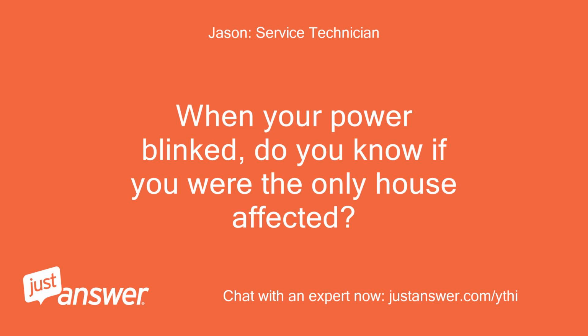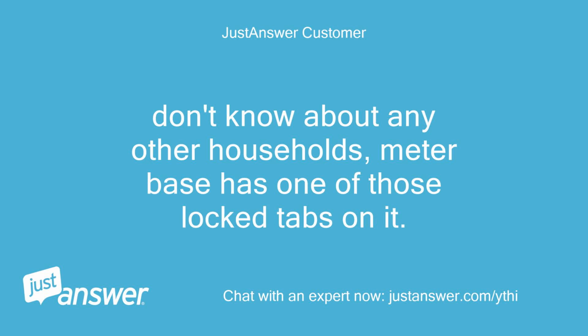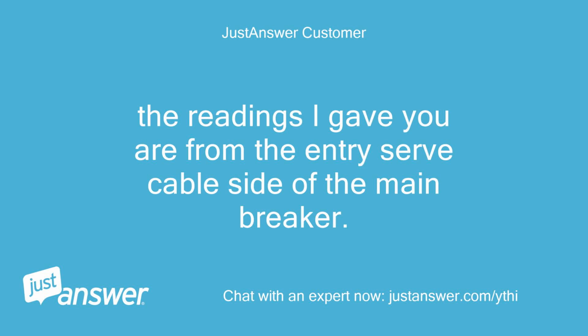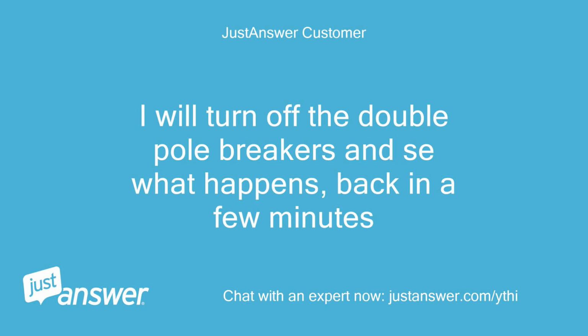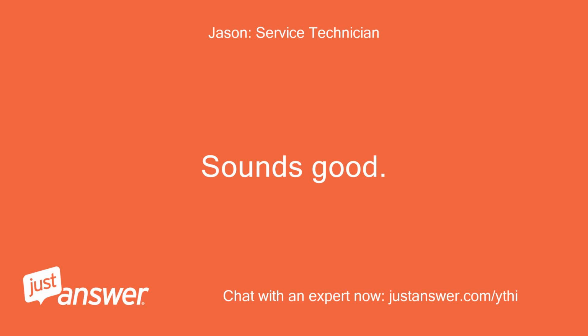When your power blinked, do you know if you were the only house affected? Don't know about any other households. Meter base has one of those lock tabs on it. The readings I gave you are from the entry service cable side of the main breaker. I will turn off the double pole breakers and see what happens, back in a few minutes. Sounds good.